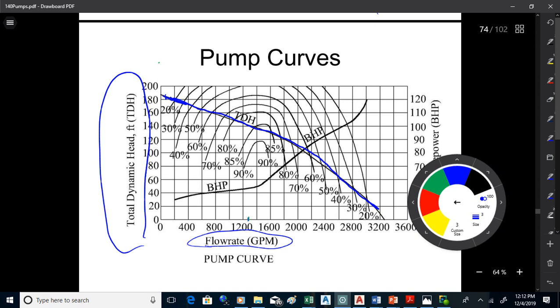And the line that I just outlined there in dark blue tells you how the pump will operate. So basically, with a pump, what you have is a trade-off between the head, which is the pressure you develop, and the flow rate. So as you generate more flow, you have less pressure, okay? So you've got a trade-off between those two things.